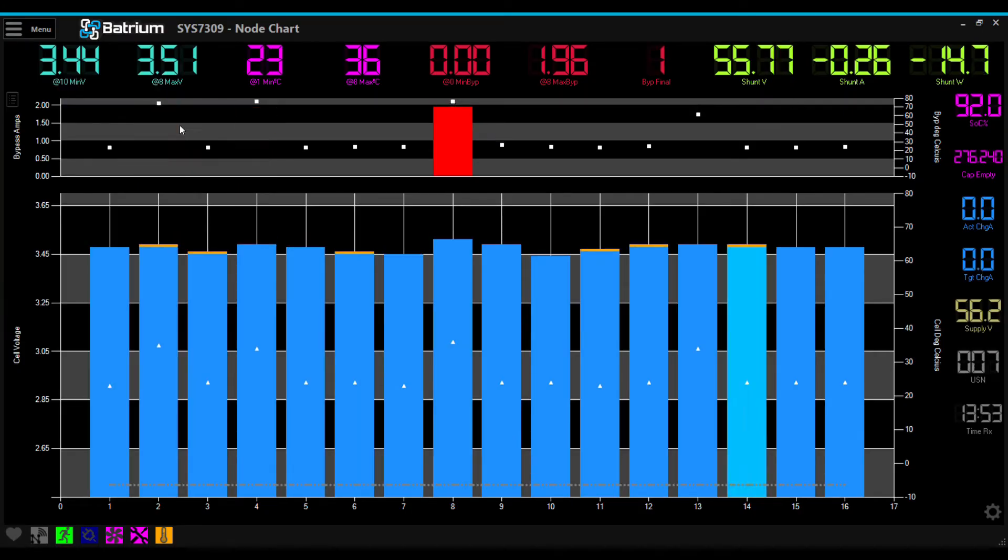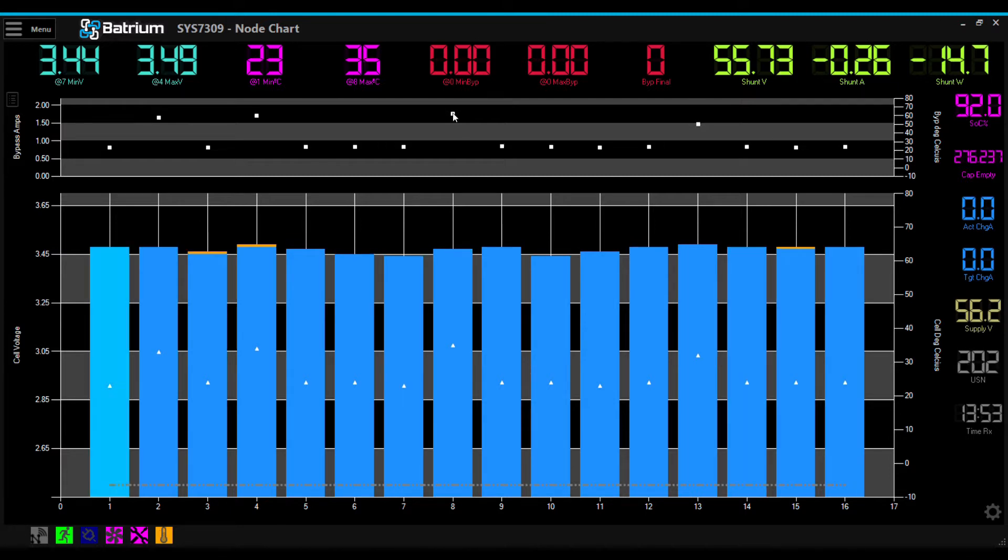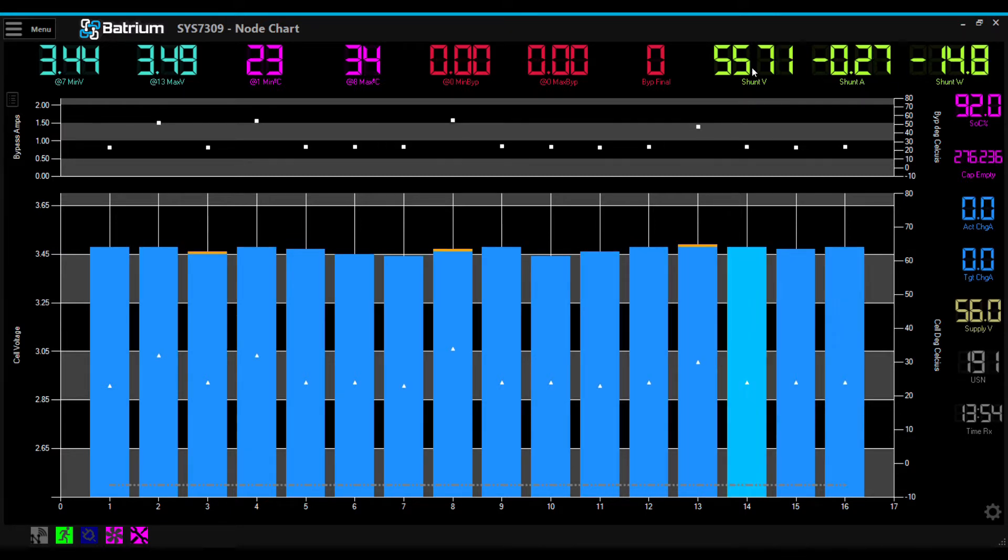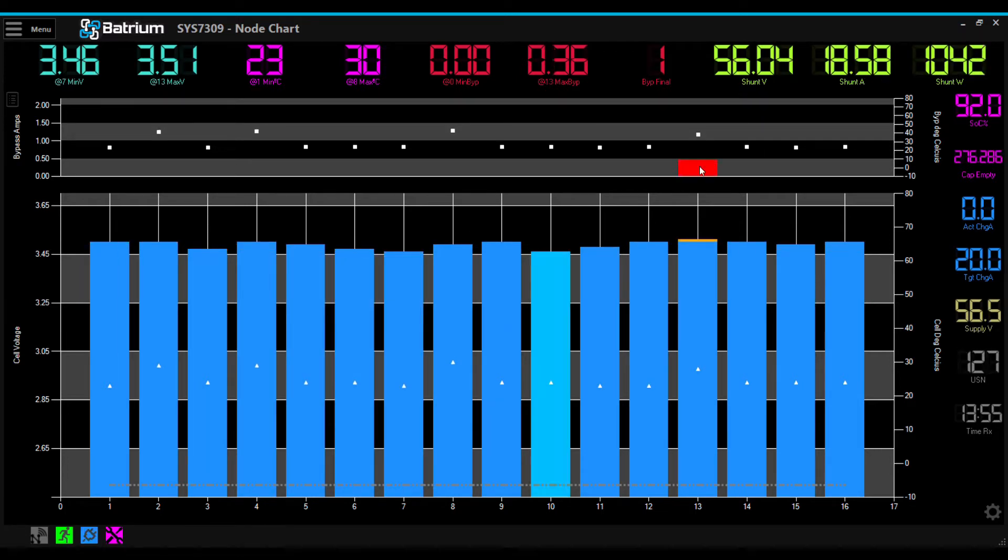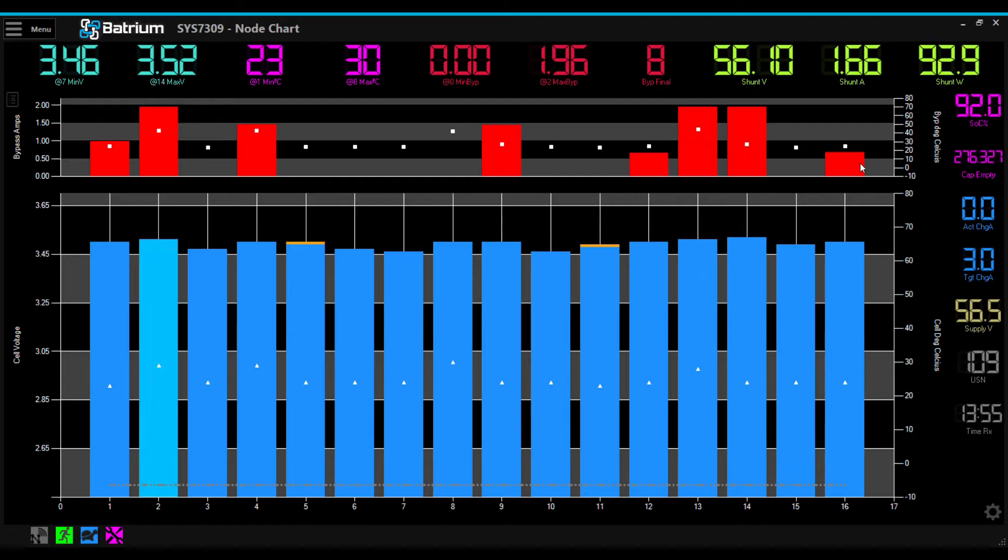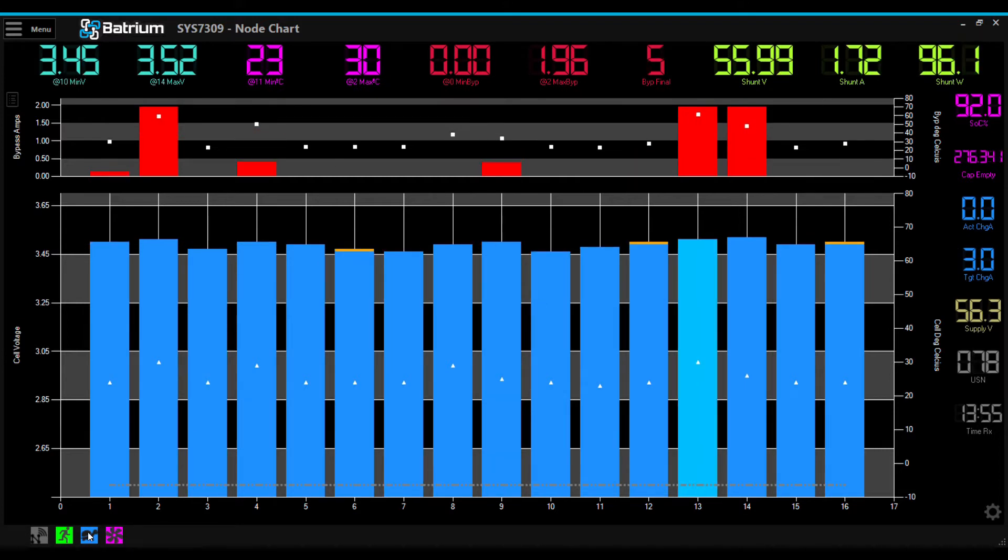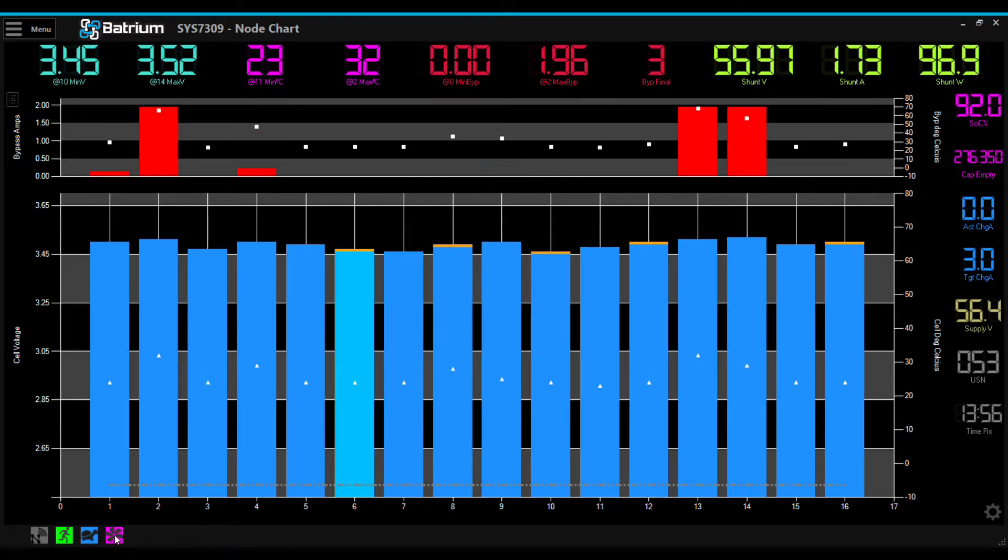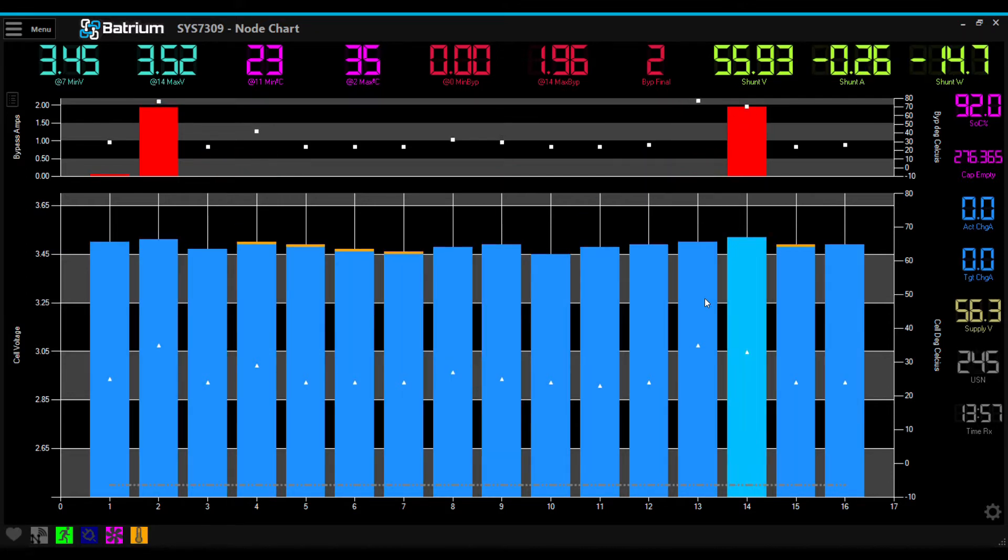This recording was taken over about half an hour as the system recorded 100% state of charge. As you can see, the cells are balancing one by one. The chart on the top shows the temperature as dots, and the chart on the bottom shows the cell voltage. As each cell reaches 3.5 volts, it will start to bleed off current.